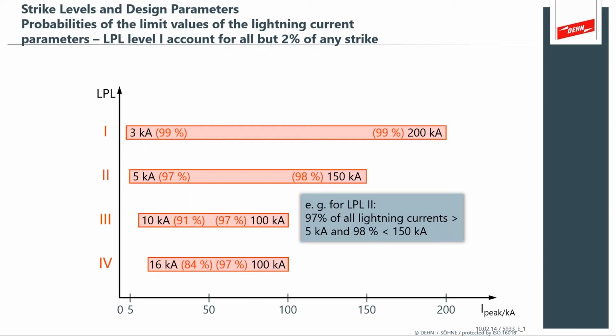And again, it's a matter of controlling the risk enough to be below the threshold, but not necessarily going overboard, because that will reflect itself in the cost of the system, both in the grounding means, the air terminals, and in SPD selection. So if you select the necessary and sufficient measures, you can control the risk and not become overly expensive. And that's reflected in the LPL class. So if you have something that looks like an explosive environment at a power plant with lots of explosive gases, then of course you want to pay much more attention to risk control. So you'll manage these high energy wrath of God strikes, but you'll also manage the low strike, because you want to account for more of the strike incidents.